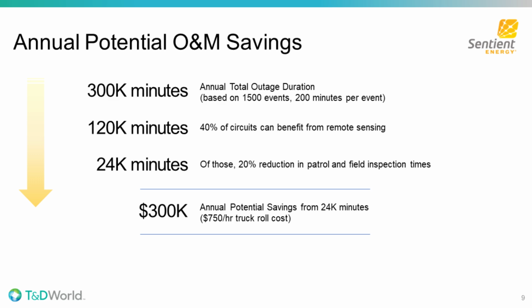If we start at 1,500 events times 200 minutes per event, we are looking at about 300,000 minutes of outage. Now, realistically speaking, there is no silver bullet for everything. We can impact, let's say, only 40% of that from an O&M perspective. This means even with that low penetration, you're looking at saving about 120,000 minutes of outage that can benefit from remote sensing. If you recall, we say 20% improvement is reasonable. This means a savings of 20% on 120K minutes is about 24,000 minutes worth of reduction in patrolling and fault finding time.